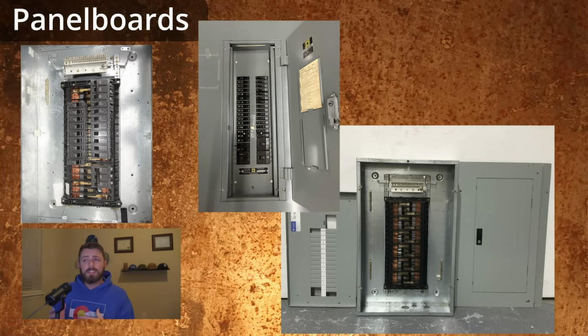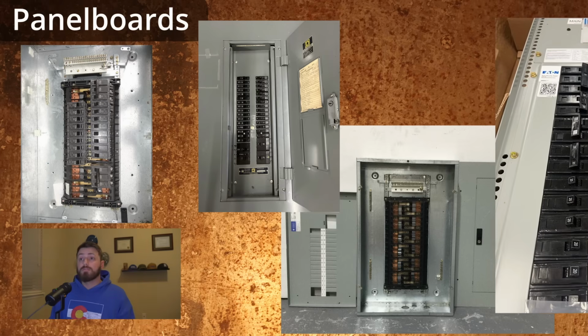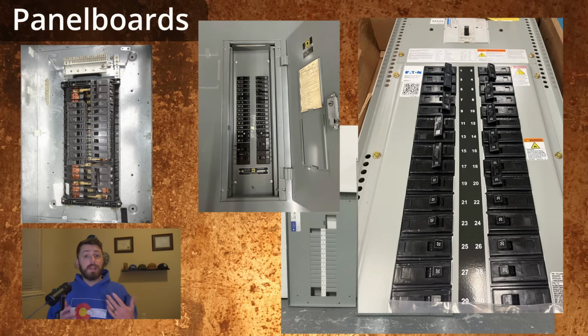Sometimes also called a load center. This type of distribution panel is found everywhere from homes to offices to industrial facilities. These are most commonly used to protect and distribute power to lighting, outlets, or other pretty small loads. They're exclusively low voltage. Here in the US, that means 120, 208, 240, or 480 volts. Sizes can range from 50 amps all the way up to 400-ish amps. Exceptions to that, I mean, you might see bigger ones.